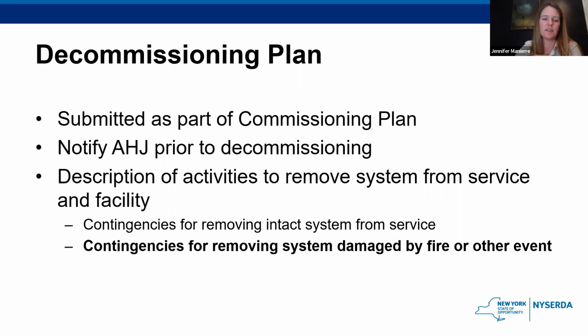And the decommissioning plan, like I said, is part of the commissioning plan. Prior to decommissioning any system, the authority having jurisdiction needs to be notified before that starts. And the plan should include a description of the activities that would take place to remove a system from service. At the end of its useful life, you might be removing an intact system from service because it's just not needed anymore, but perhaps more importantly, that plan needs to outline how you're going to go about removing a system that was damaged by fire or some other event. Sort of the unexpected decommissionings, if you will.